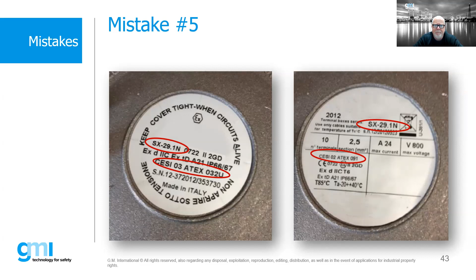This is an example of the same product. If we look at the label here of these two devices, it's actually the same part number, right? It's an SX29-1N. We see that. But if we notice on the left-hand side, we see that it has a U certificate. On the right-hand side, it does not. So the one on the right-hand side is a small little flame-proof box that has 10 terminals rated at 2.5. It's a fully certified enclosure, and it has a T code. The one on the left-hand side is the exact same enclosure, but it was supplied without any terminals on the inside. So it's a component certified product, not an assembly certified product.